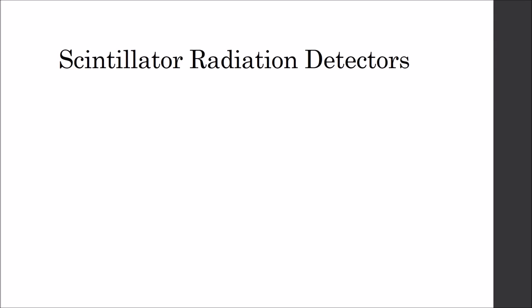A scintillator-based radiation detection system operates by having a scintillator react with radiation to produce light. A photo multiplier is then used to detect that light and produce electrical output.